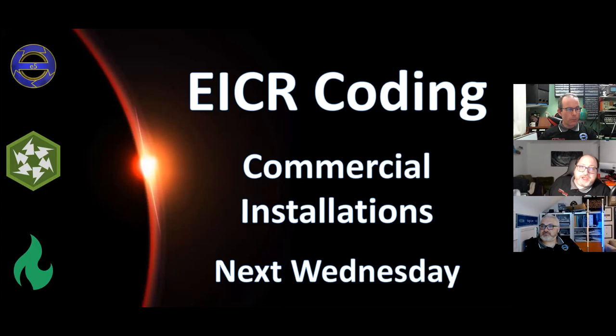Daniel would like clarification on 433.3.1, the omission of overload protective devices for the characteristics of the load if it's not likely to carry an overload current. Resistive loads are given here, so resistive loads are considered not to need overload protection. But what if the equipment has capacitive components, inductive components, electronic components? Does that mean it now could overload?